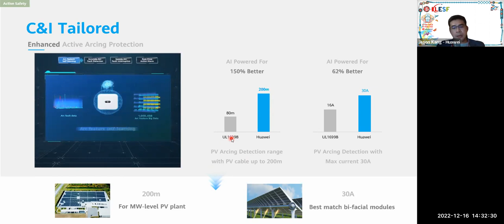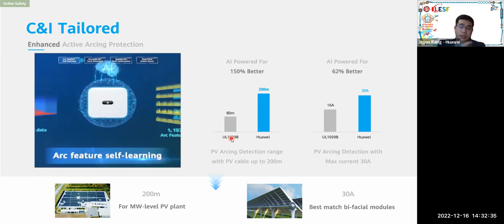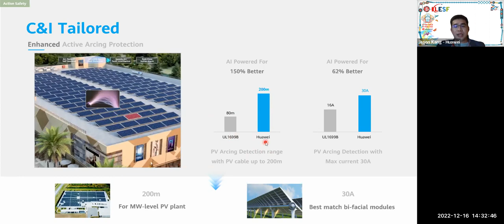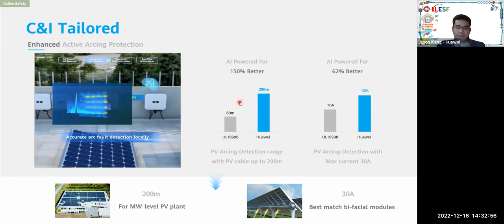And when an arc fault is confirmed, the inverter will be turned off in less than 2.5 seconds. Now, that is based on the IEC standard out there: 2.5 seconds. The inverter must be turned off via the AFCI function. But for our inverter, it can be turned off in less than 0.5 seconds. So as you can see over here, the standard out there is 80 meters in terms of the PV cable detection range. As the cable, the positive cable and also the negative cable, is longer, the arc signal will actually drop, right? So to detect it is harder. But if you look at what Huawei can provide, up to 200 meters, our AFCI will be able to detect an arc fault, which is 150% better than the standards out there, right?